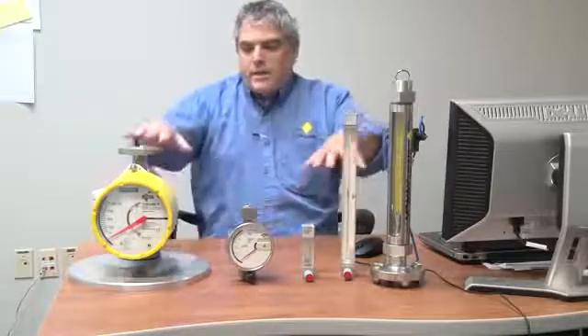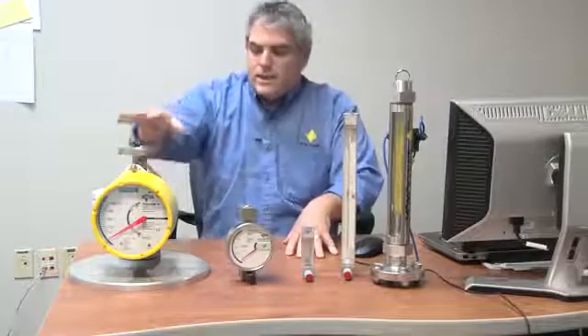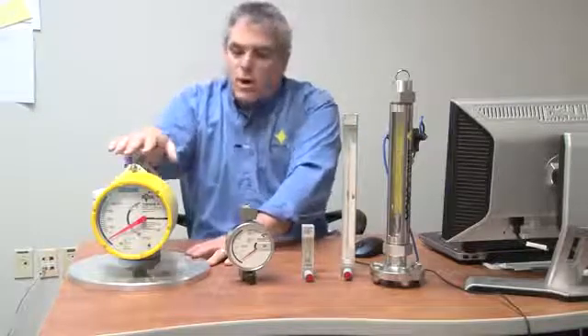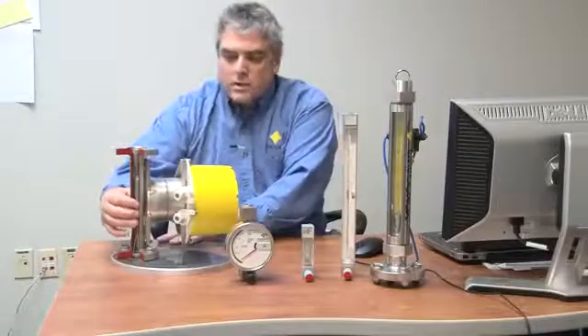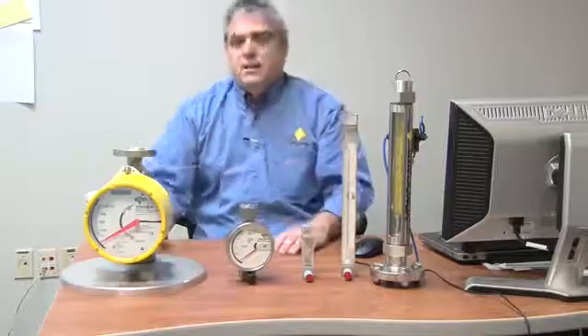One of the great applications of the rotameters is that they are easy to install, easy to maintain, and because there is no external electricity required, and this is an entirely mechanical device, little or no maintenance is required. No calibration is required because there is nothing that can fail.